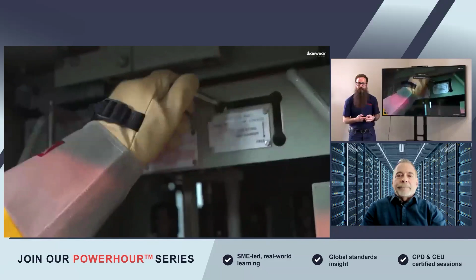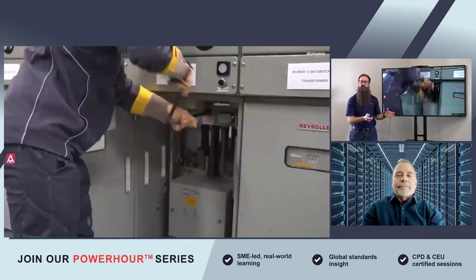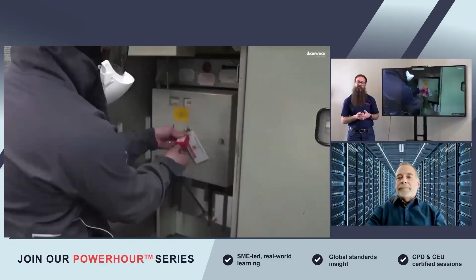So in this example, we're going to use the switchgear to ground the circuit. So we've put that switchgear into the circuit earth or circuit ground position. So the front contacts are going to enter the circuit orifice and come into contact with those spouts. And on the back, we've got ground pins or earth pins which connect to the substation ground. So then they're both in contact. We'll make sure interlocks are correct, charge the springs, and we'll close that circuit breaker to then ground everything from the primary side of the transformer, the cable, down to the substation ground through that circuit breaker.